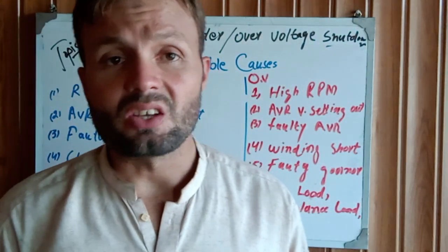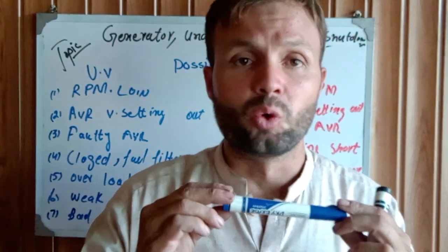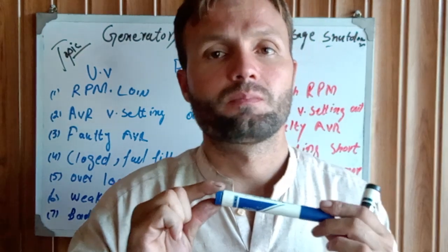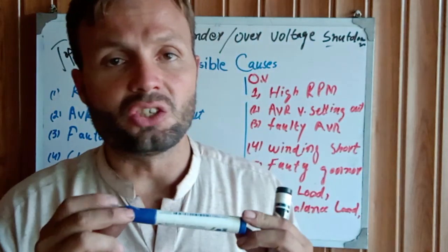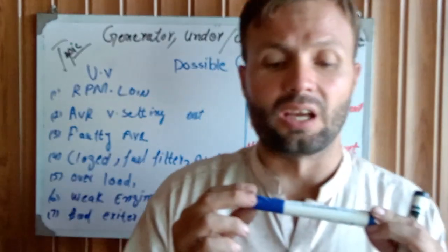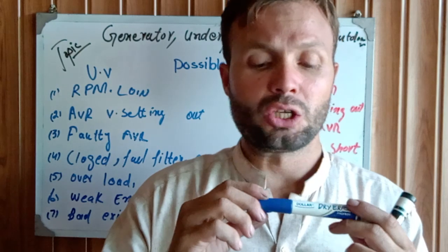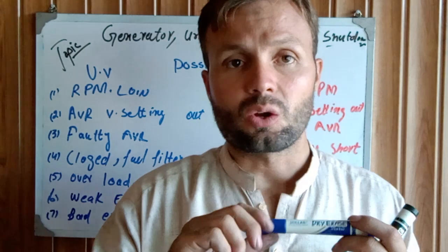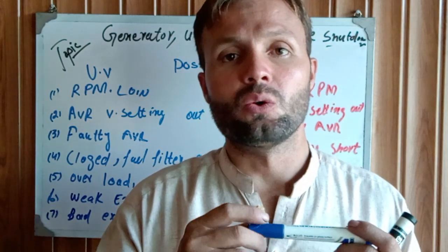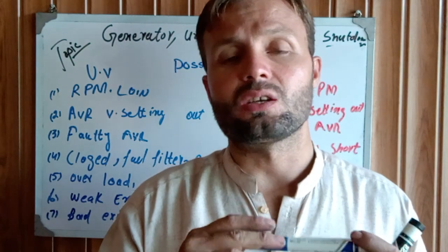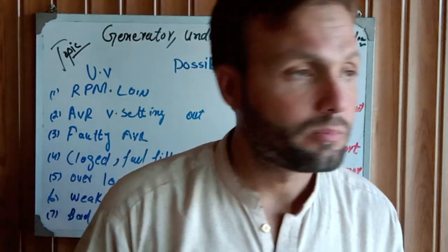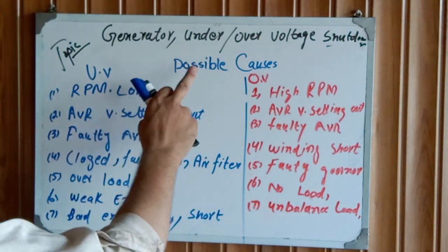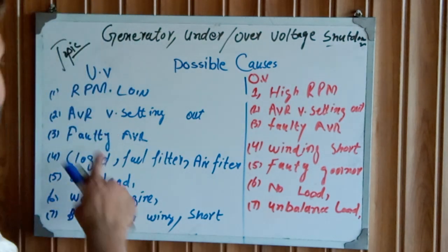The engine RPM is set using the engine fuel injection pump. On the diesel engine fuel pump linkage, there are bolts — when you tighten the nut or bolt clockwise, the RPM increases, and when you release it counter-clockwise, the RPM decreases. First of all, you need to set the correct rated RPM for your engine according to the engine specification.